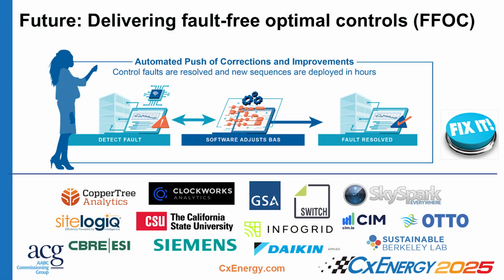So we had a paper published a few years ago around some internal folks working on an active test to tune PID loops that are hunting in a VAV reheat box. So that's a really advanced application. Today I'll be talking about functional testing and how this process can be used to automate that functional testing that folks see in commissioning workflows. So this is the future we're talking about. The project that we're doing this work in is called Fault-Free Optimal Control, so FFOC for short. And we're trying to get folks to this kind of paradigm where you can detect the fault, and the same software that is overlaid on the BAS can be used to push a fix back, empowering building operators or managed services providers to give them a fix-it button, right?